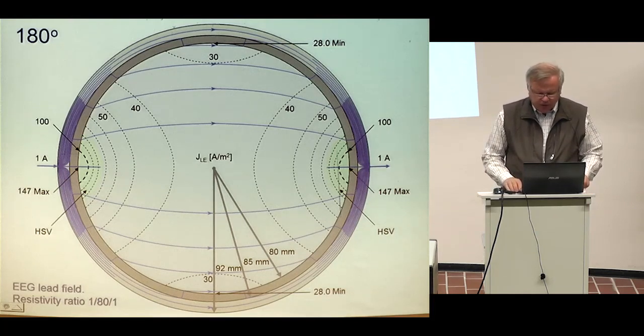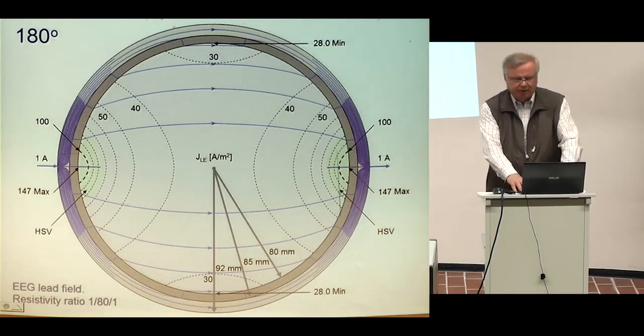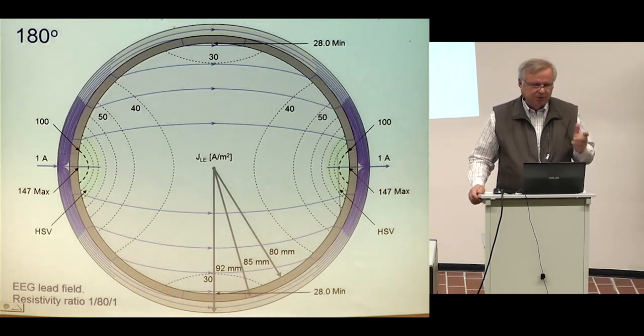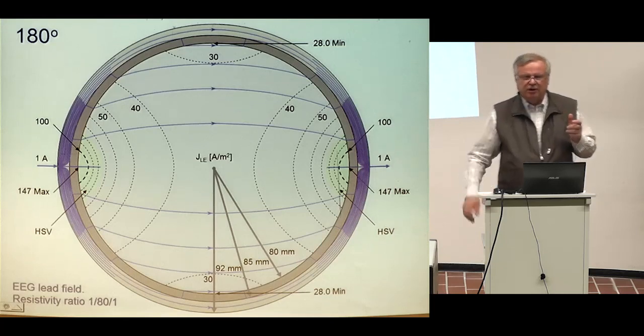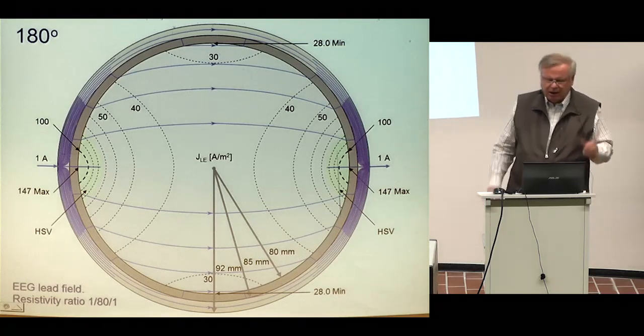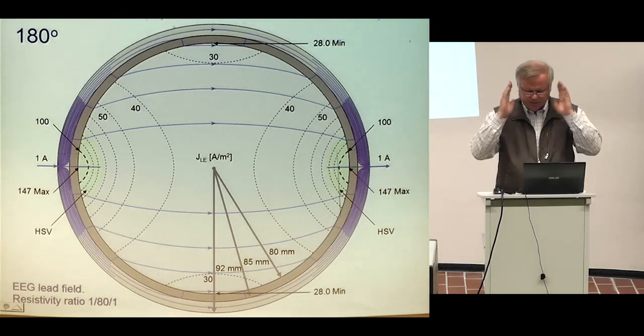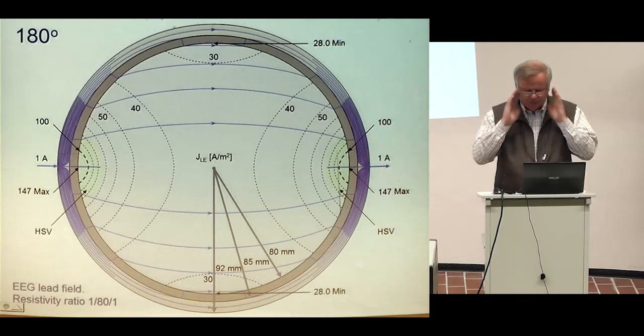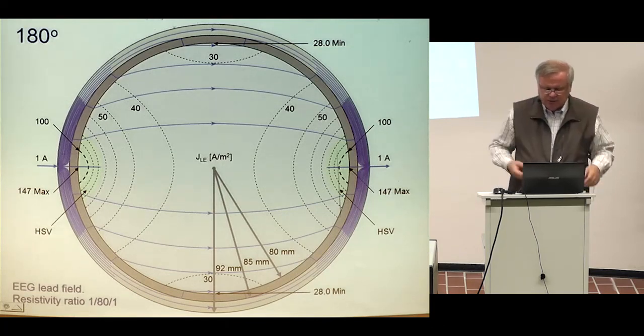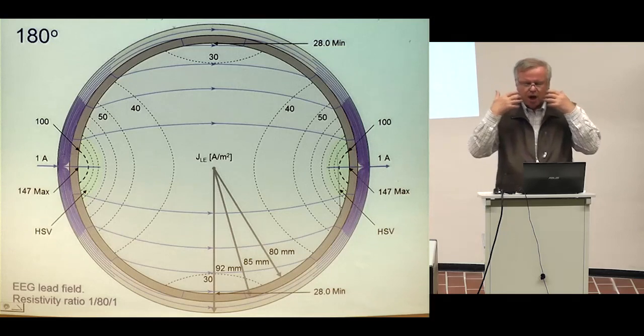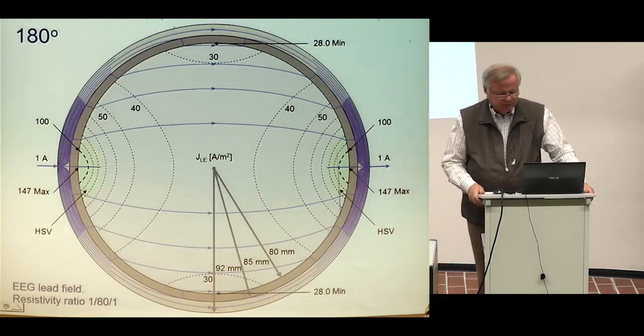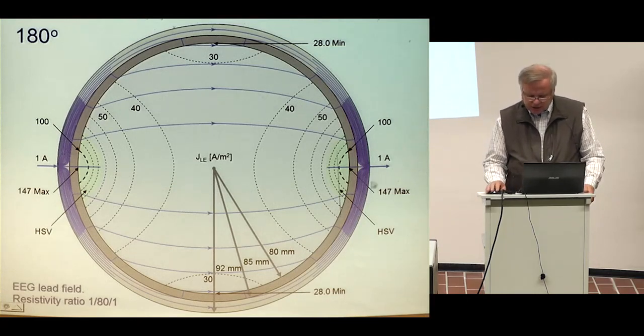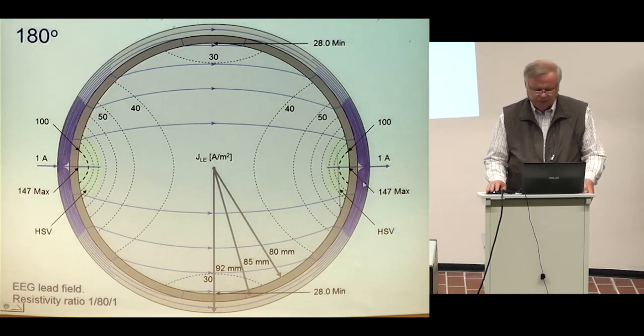From this first picture you learn that what the EEG measures primarily is the electric activity on your scalp. That is important because it is a source of noise. On the sides of the head there are muscles on the scalp — not on the top, but on the sides. So if the muscles are activated — eyebrow or jaw muscles — they generate strong noise because the measurement sensitivity there is high.